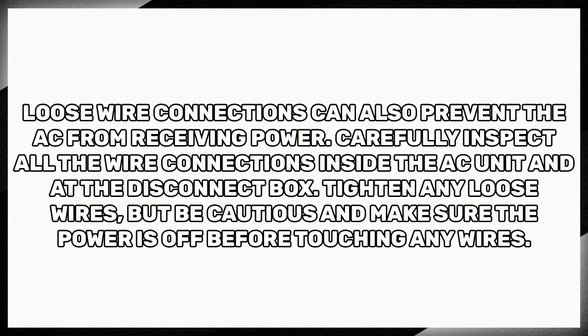Loose wire connections can also prevent the AC from receiving power. Carefully inspect all the wire connections inside the AC unit and at the disconnect box. Tighten any loose wires, but be cautious and make sure the power is off before touching any wires.